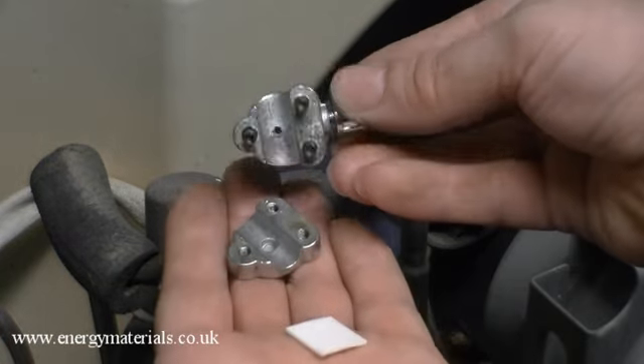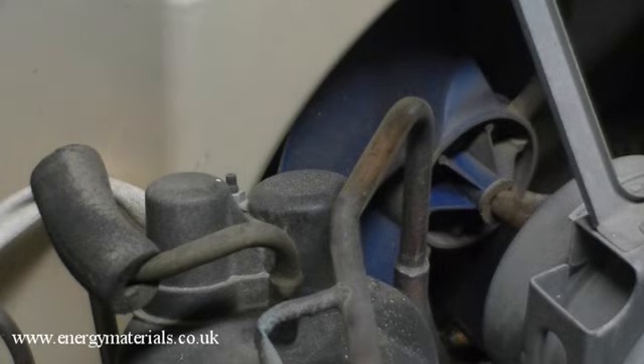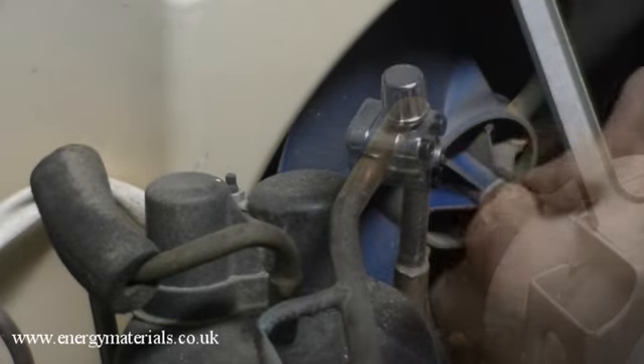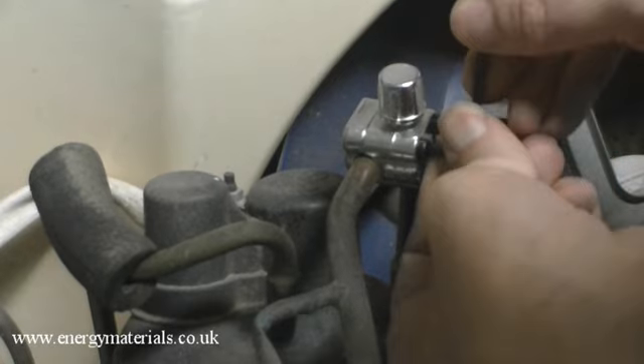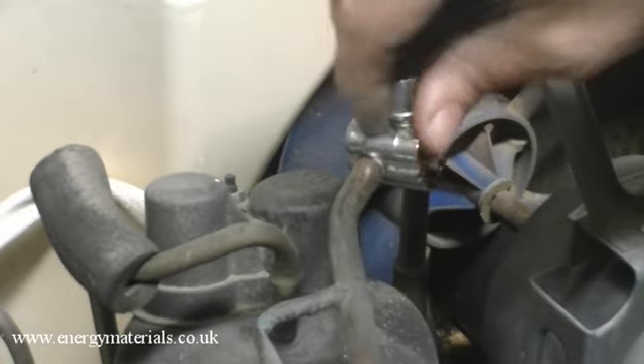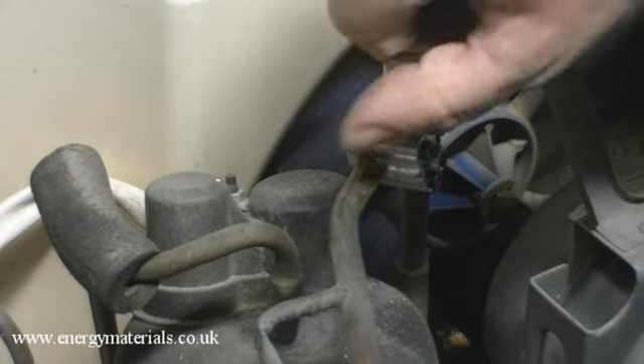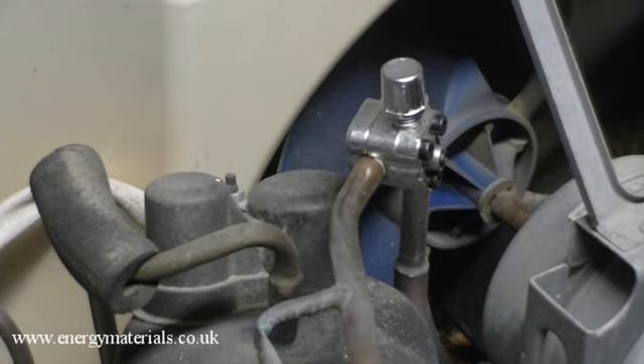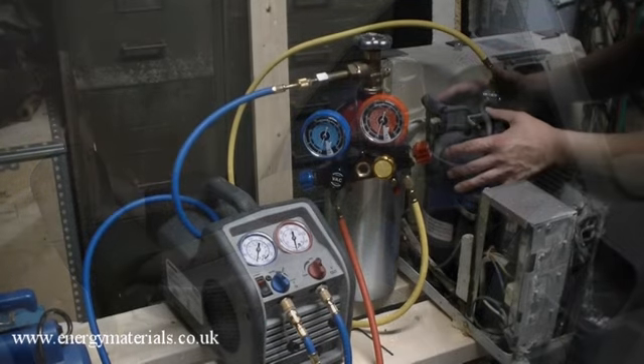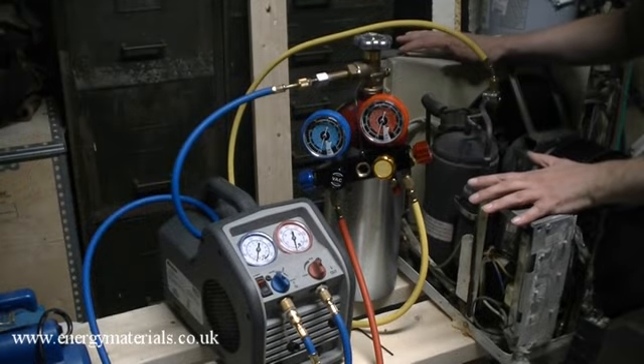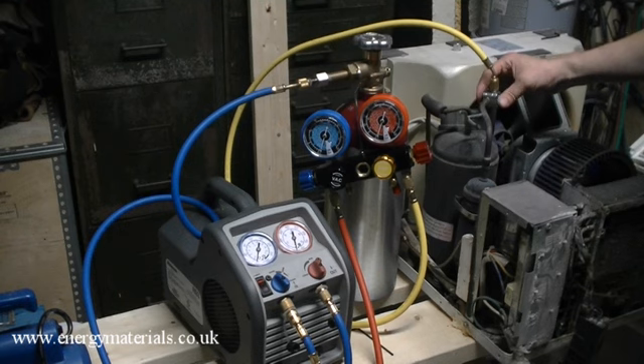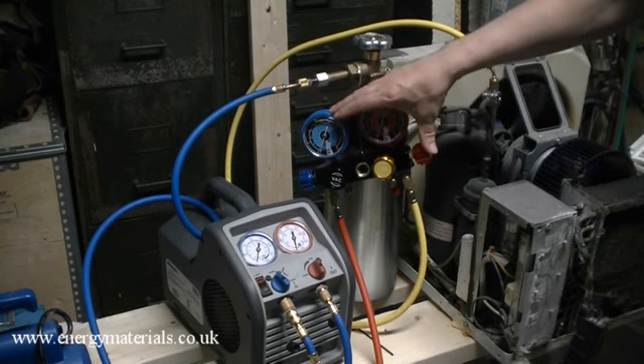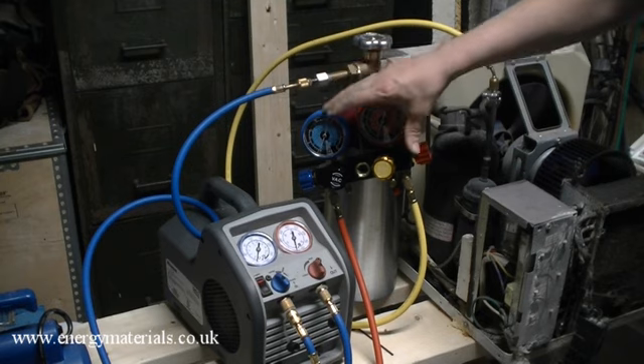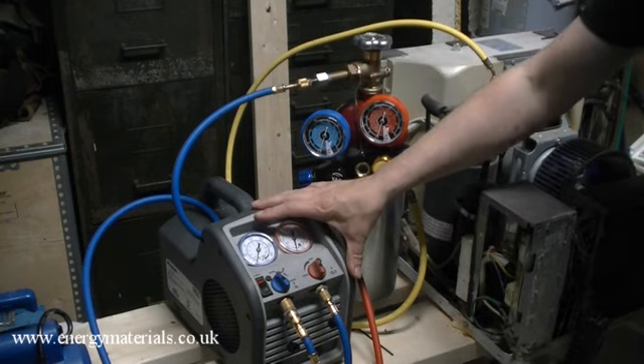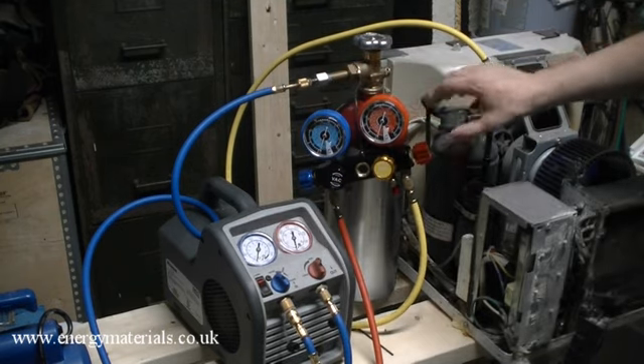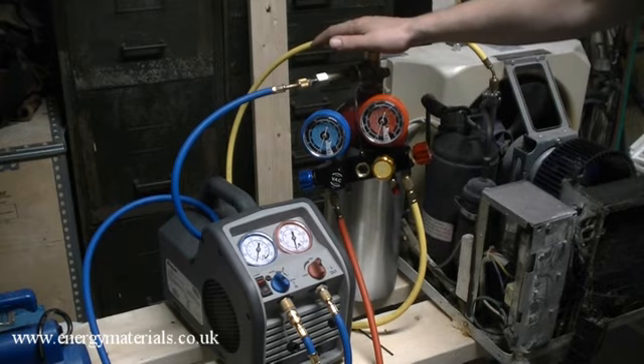The next step is to extract the refrigerant from the AC unit. As the line set is sealed without access valves, we're going to perform a hot tap into the line set with these piercing valve adapters that we're going to attach to the copper tubes. So we're going to recover the refrigerant from our compressor, our line set, in this window-based AC unit. So we've got to connect it. There's a pierce valve there we need to actuate. That's connected to a couple of gauges so we can monitor and control what's going on. These gauges are connected to a recovery machine, which is going to pump the refrigerant out of our window AC unit and into our tank where we're going to recover our refrigerant.